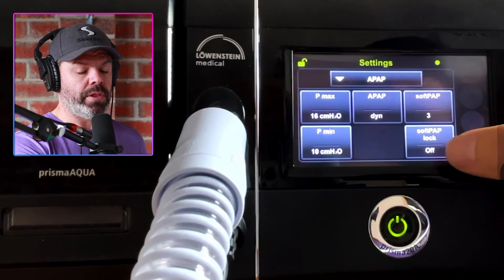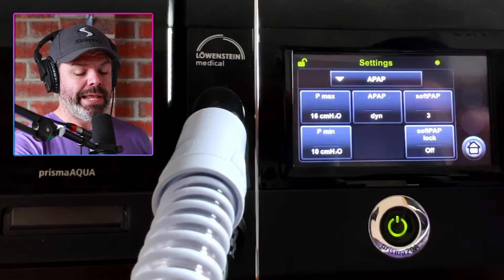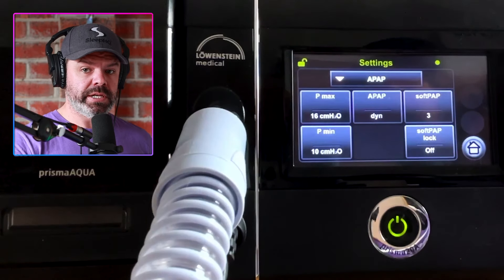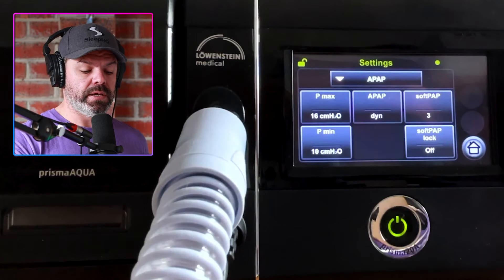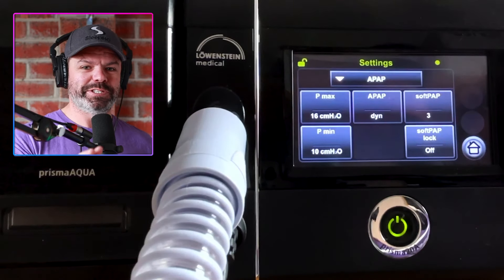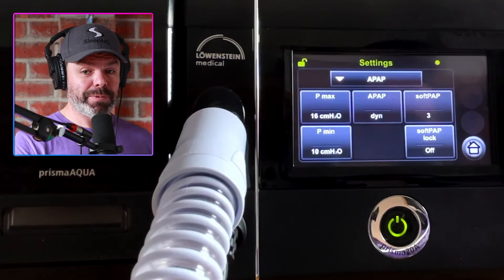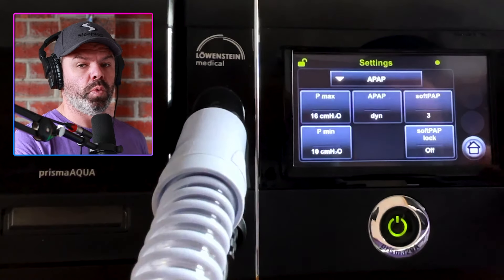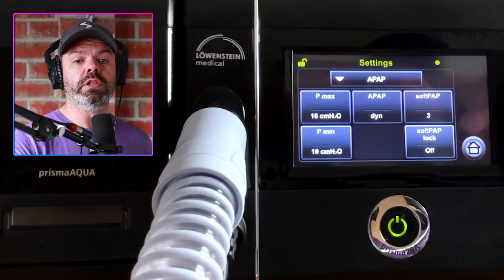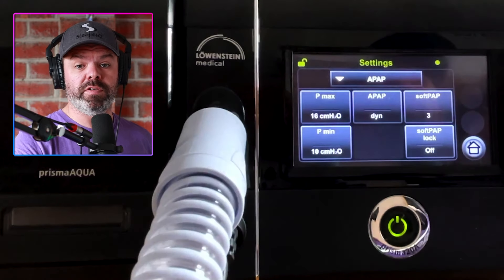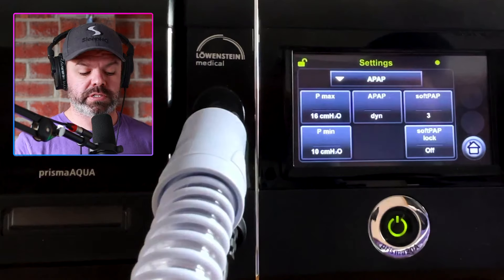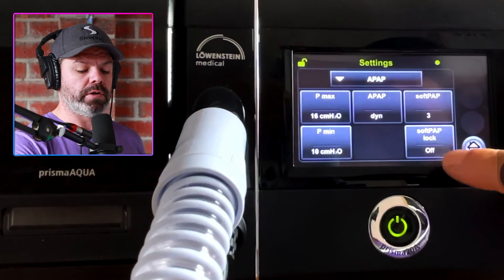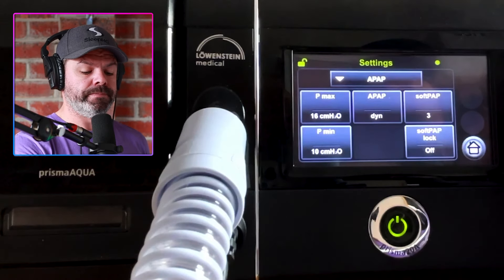Soft Pap lock — because we're in the clinician settings, clinicians have the ability to lock different settings if they choose to. We want to turn all the locks off so we have access to all the settings, so Soft Pap lock should be off.